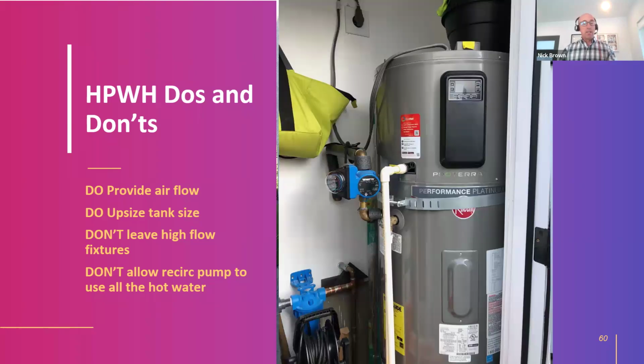Also consider upsizing the tank. I put a 50-gallon in for the ADU and a 50-gallon in for the main house—we have 4 people in this house sometimes a year, no problem with 50 gallons. But some of your clients with large families are going to want an upsized tank, 65 or 80 gallons. If you would typically put in a 50-gallon gas water heater, it's a good rule of thumb to put in a 65 or 80 with heat pump water heaters, because they recover a little more slowly.